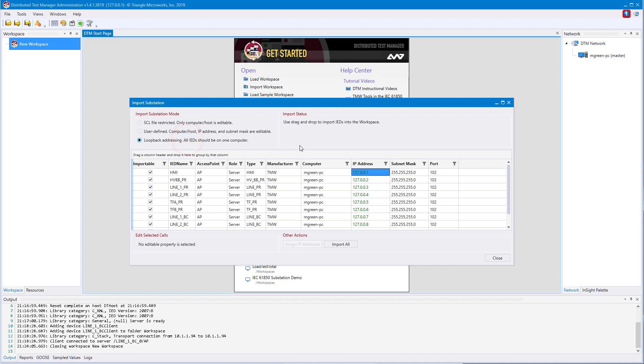The last mode is loopback addressing. This mode is the quickest way to get from nothing to a full simulated substation. Every device in your substation will be assigned an IP address in loopback addressing. This means devices outside of your computer will not have access to this simulated substation, but you'll be able to connect to everything locally.